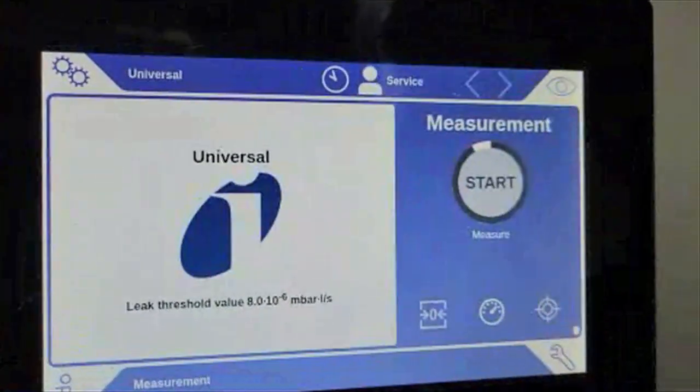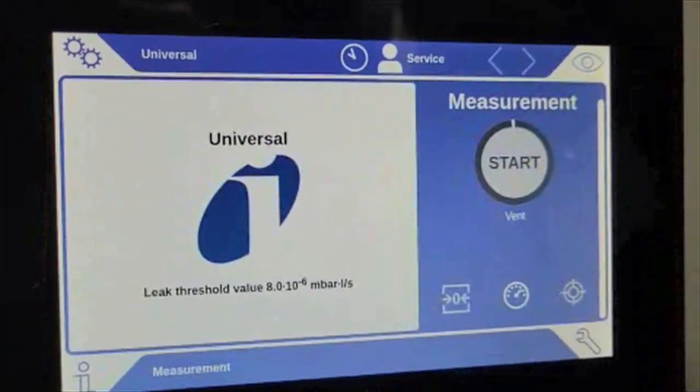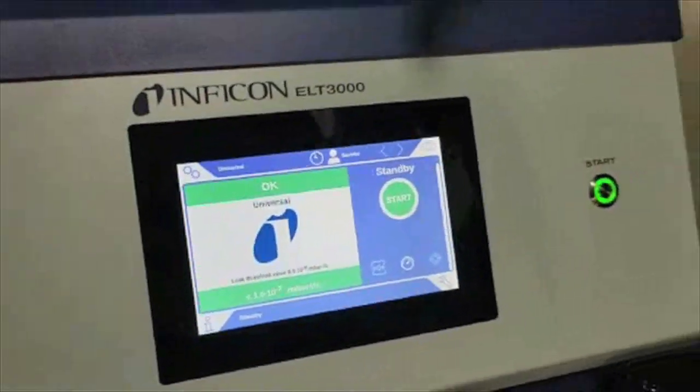Customer leak rates for battery pouches should be around 1 times 10 to the minus 5 millibar liter per second. With this empty chamber representing a good part, we're going to see no value higher than 1 times 10 to the minus 7 — that's a hundred times less than what we're expecting to see.